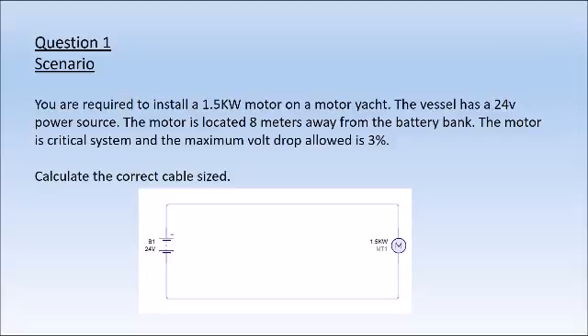We are going to start looking at volt drop. Within an exam paper you'll get a question — they can be quite wordy — so what we need to do is read the question, break it down, and establish what we need to do. You are required to install a 1.5-kilowatt motor on a motor yacht. The vessel has a 24-volt power source. The motor is located eight meters away from the battery bank. The motor is a critical system and the maximum volt drop allowed is 3%. We need to calculate the correct cable size to maintain that maximum 3% volt drop in that circuit.